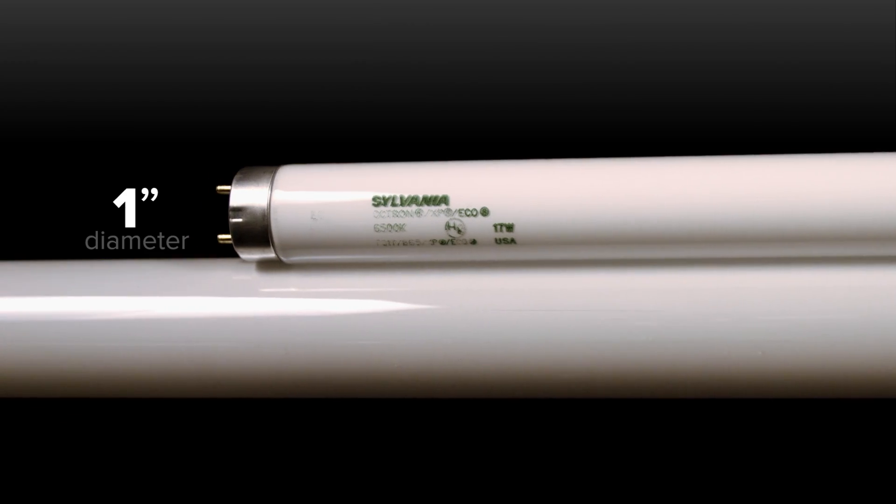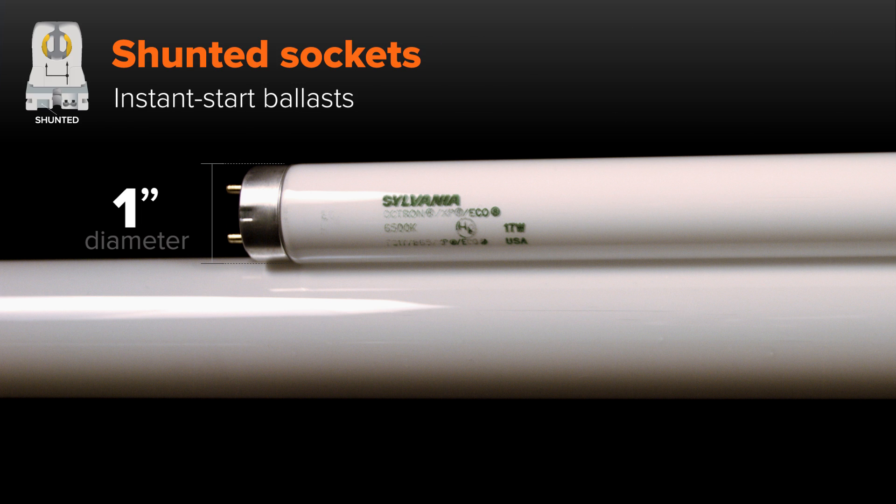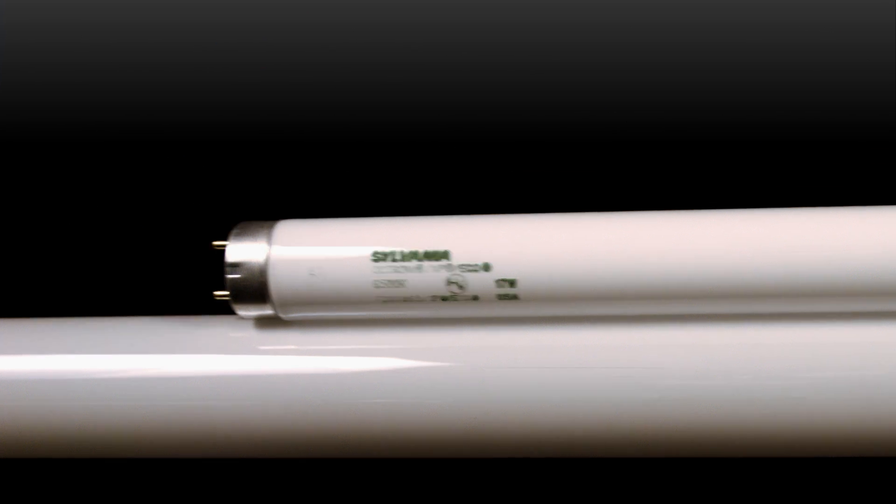T8 tubes, which are one inch in diameter, can use either kind of socket. When paired with a rapid start ballast, program start, or dimming ballast, T8 tubes typically require non-shunted sockets. When paired with an instant start ballast, T8 tubes typically require shunted sockets.